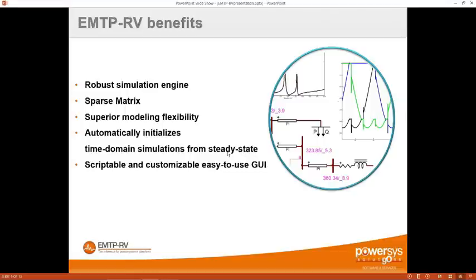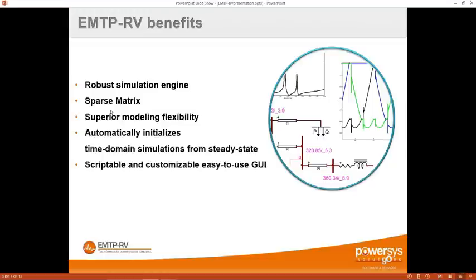Here are the benefits of EMTP-RV compared to other transient software. First, it's a very robust simulation engine in terms of solving non-linearities — we use iterations within each timestep to find exactly where we are on the curve for non-linear elements like IGBTs, surge arrestors, and saturations. We also use sparse matrices to solve the network, which makes a big difference for large networks, since simulation time and memory usage increase as the cube of the network size.